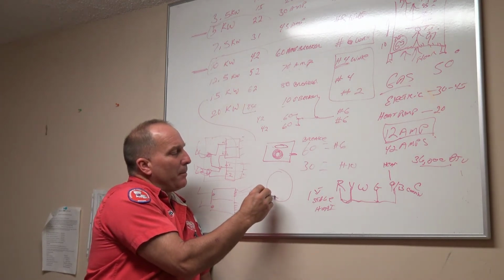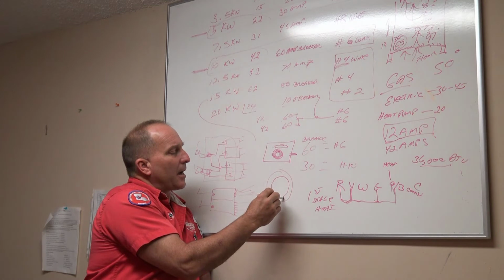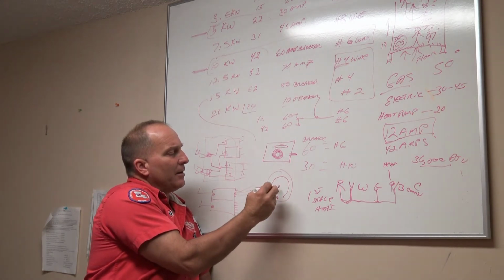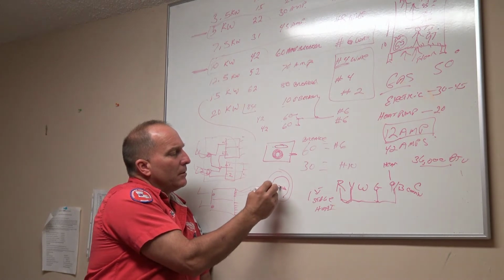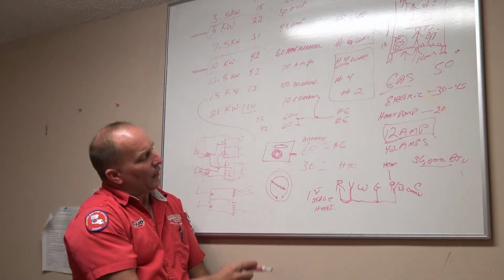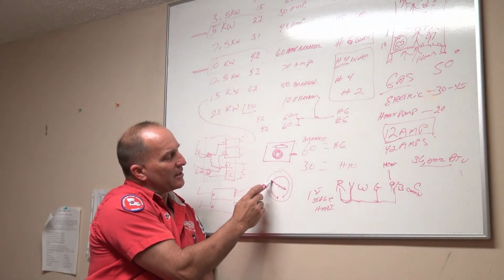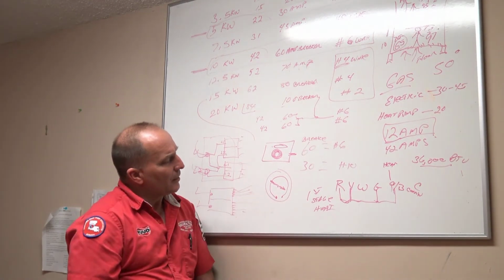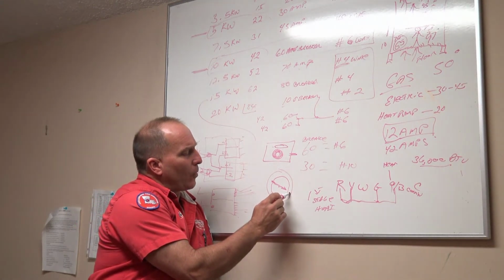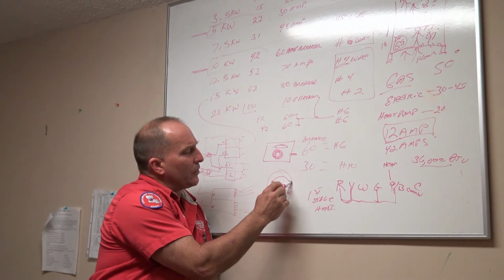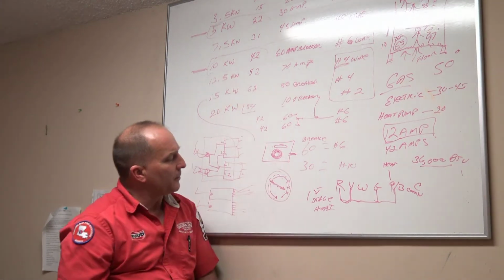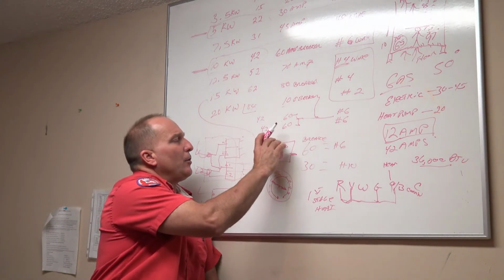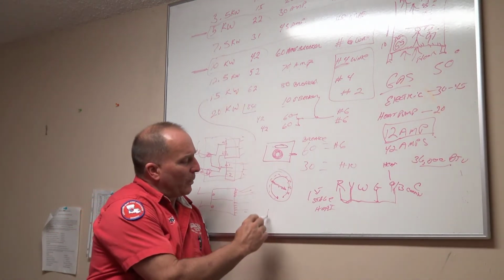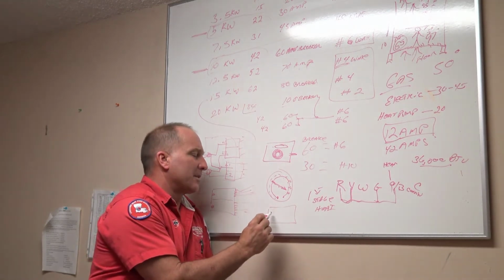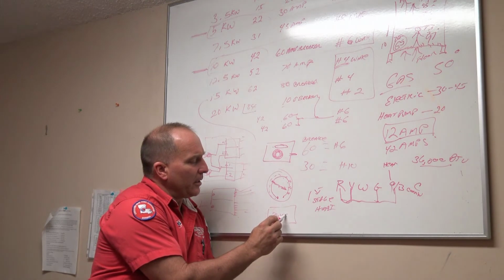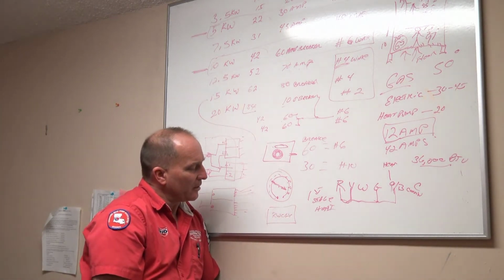In that disc, there is a metal wire that runs around like this and stops here and stops here. Inside there, there is an arrow. Now notice that arrow does not touch this side, but it does touch this side over here, okay? So I'm going to call this 0.04 right here, 0.03 right here, 0.02, 0.01, and it comes around with other numbers here. You take this part of your thermostat off, and you're left with the bottom of your thermostat, called the base, and you have R, W, C, G, Y, because you're not having 2-stage with this thermostat.